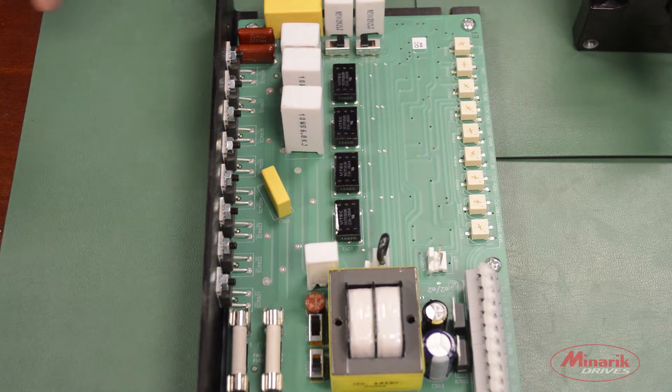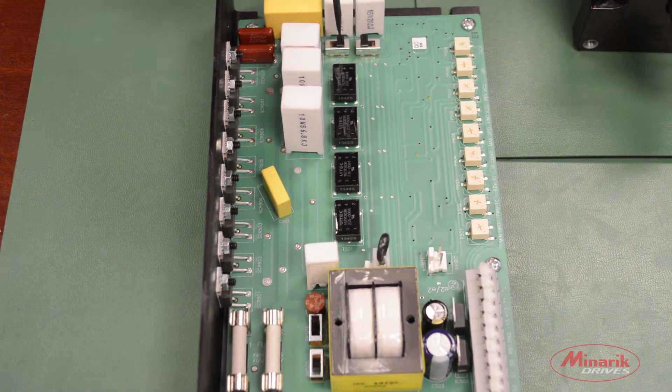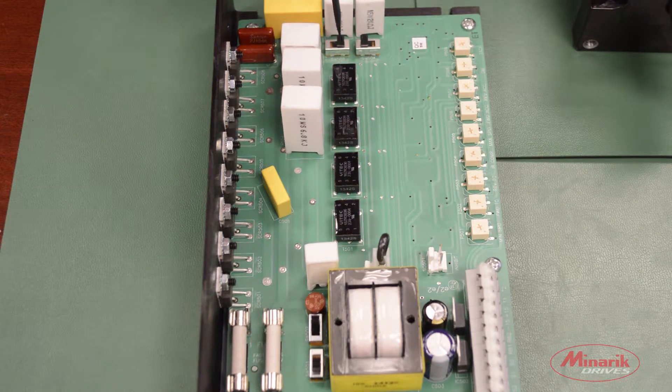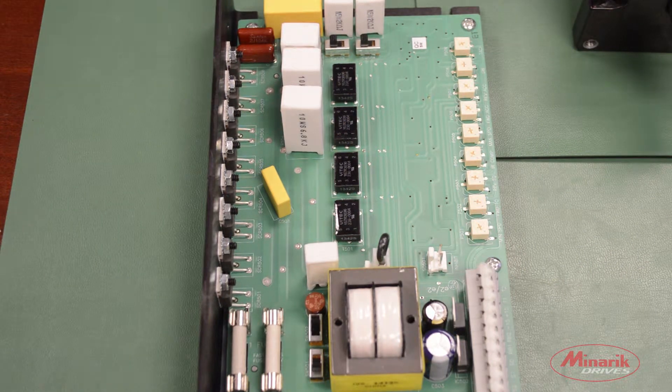The output voltage switch is located at the end of the drive and it's factory default set for 180. We're going to be using a 90 volt motor so we'll move that to the 90 volt position.